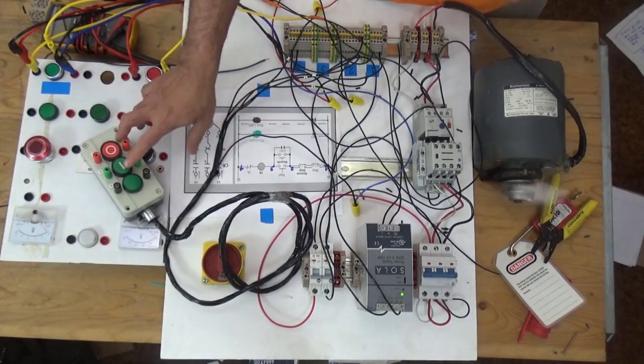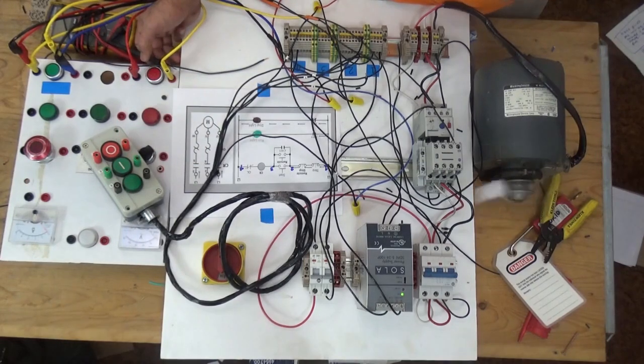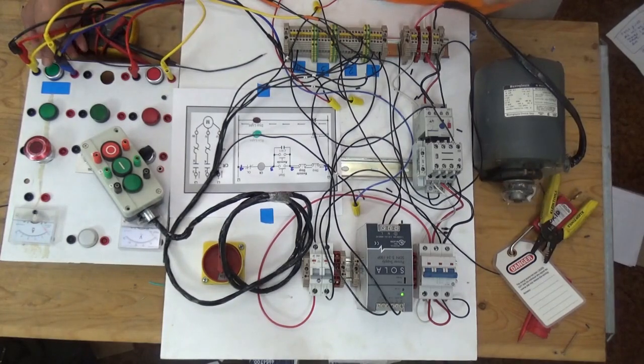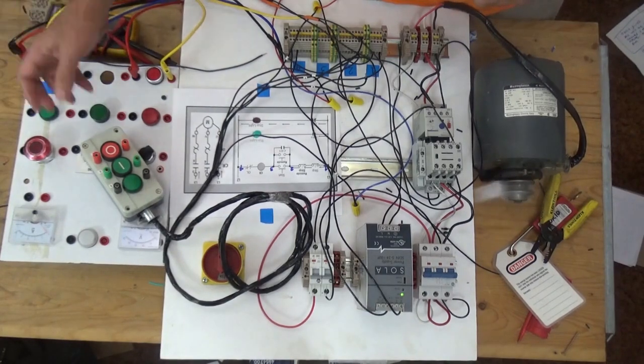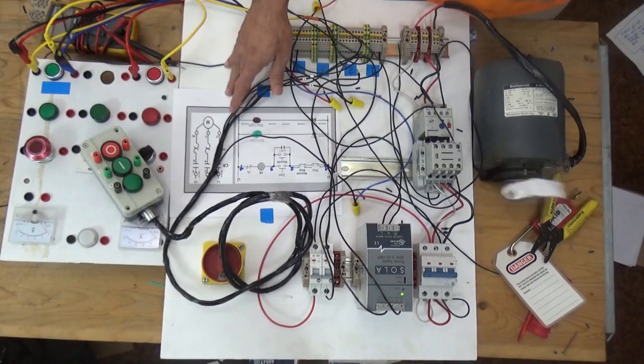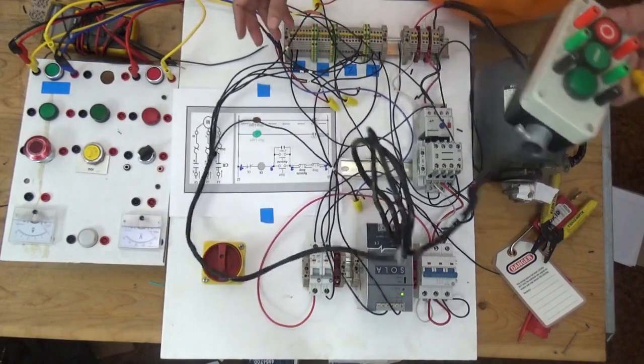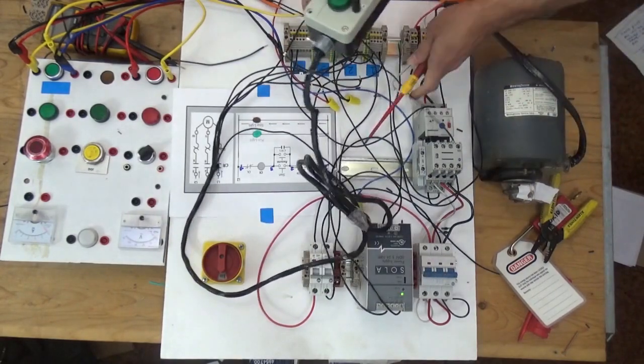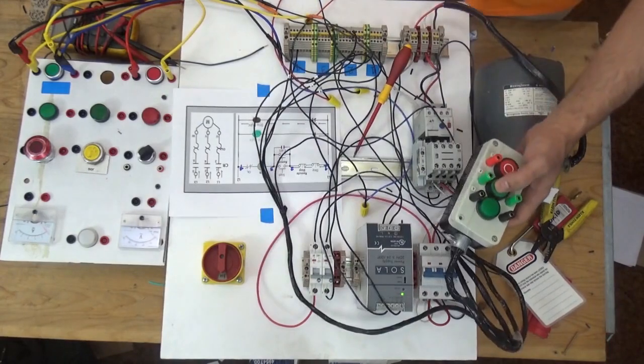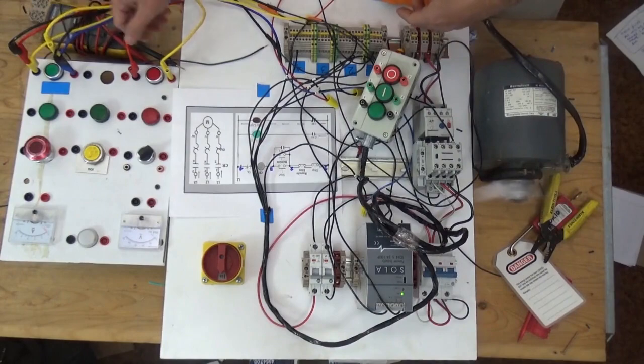This time it should latch. When you are going to push the start button here, you can press the stop button here. That is multiple start-stop. If I'm going to press the start here, I can stop it here. So even though you are hundreds of feet away, you can still start. See this one? You go to the other location, stop it.